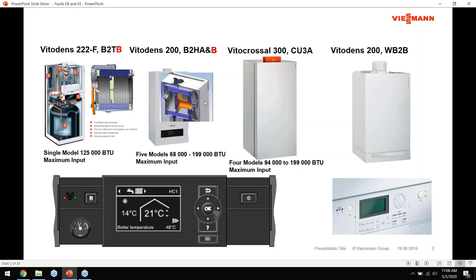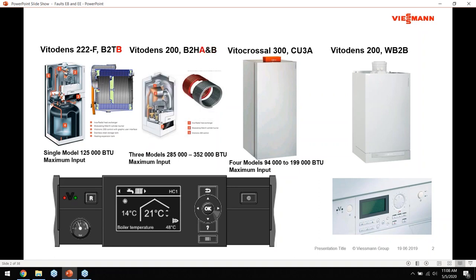Next we have 10 models of the B2HA and B2HB boiler. A lot of you work on these units - you can find them in residential standalone applications, multiple boiler applications, and commercial settings with up to about eight boilers on a cascade system. The first five boilers in the B2H series are second generation, from 68,000 up to 199,000 BTUs maximum input, with a very similar heat exchanger to the B2TB with the same baffle plate concept.